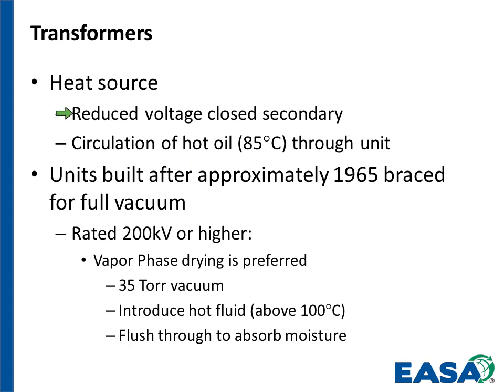In a pinch, one method for producing heat inside the transformer is to close the secondary of the transformer. In other words, to actually short the three-phase leads of the secondary of the transformer together, and then apply reduced voltage to the primary of the transformer. And by that means we generate enough current and heat to heat and help dry this.